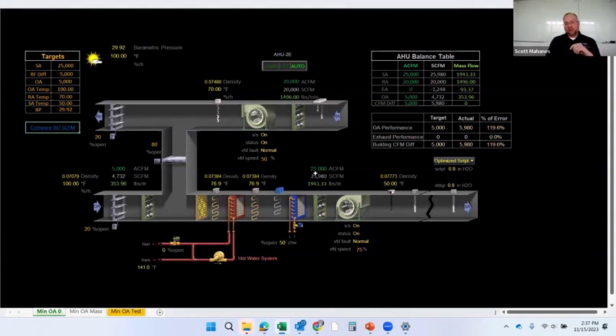And so in green, you can see my volumetric ACFM values. Traditionally, we think that if we're moving 25,000 CFM, and we subtract the outside airflow station set point, we should be tracking the return fan to that difference. So 25,000 minus 5,000 is 20,000. And in green, this table looks like you're tracking this correctly. The problem is if you convert these values into the mass flow standard CFM values, the math doesn't work out like you think it does. And in reality, what we do in standard CFM at those points yields, in this case, an excess of 980 CFM of outside air. So I have almost 20% more outside air than I want just because it's a mass flow imbalance. So volume alone cannot control my system correctly.